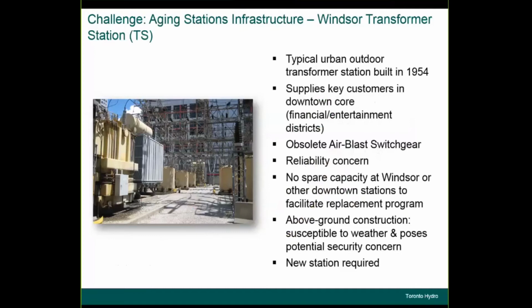It's a typical urban outdoor transformer station built in 1954, supplying customers in the financial and entertainment district. The medium voltage switchgear is obsolete air blast switchgear, which is a reliability concern. There are no parts, and we're spending a lot of time machining replacement parts to keep this medium voltage gear alive.